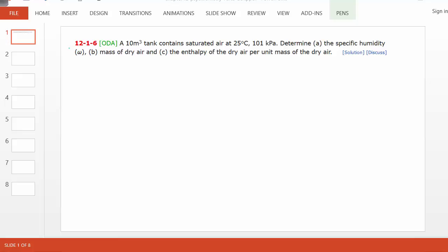So remember the saturated line, phi equals 100% humidity. See, these are the humidity values, 90% line. This is the 100% line. And 25 degrees is also written here. So this is exactly our state. So we located the state on the 100% humidity line and dry bulb temperature. Now that we know the state, we can read off a lot of variables here.